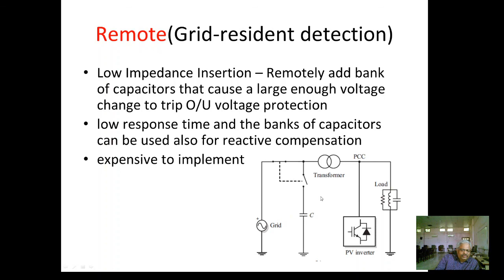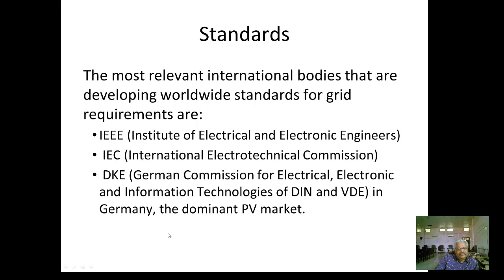Now we'll see about the standards. The most relevant international bodies that are developing worldwide standards for grid requirements are IEEE, IEC, DKE, DIN. These are the standards. Islanding-related international regulation standards are, in India, IS 16169 same as IEC 62116, and IEEE 1547. This replaces the standards: US standard, Japanese standard, Korean standard. These are the different standards related to islanding.